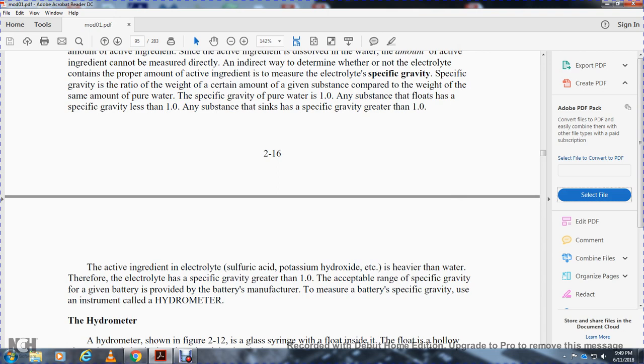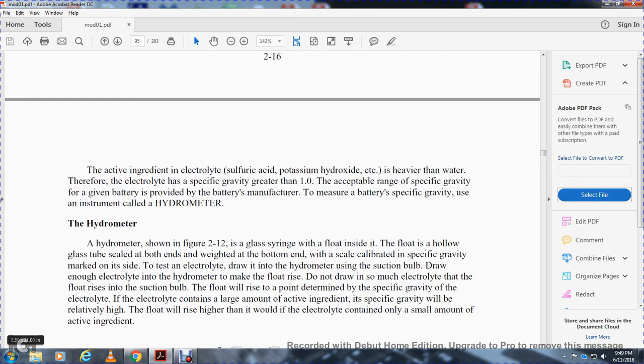Any substance that floats has a specific gravity less than 1.0; any substance that sinks has a specific gravity greater than 1.0. The active ingredient electrolyte — sulfuric acid or potassium hydroxide — is heavier than water, therefore the electrolyte's specific gravity is greater than 1.0. The acceptable range of specific gravity for a given battery is provided by the battery manufacturer. The instrument used to measure battery specific gravity is called the hydrometer, shown in figure 2-12.